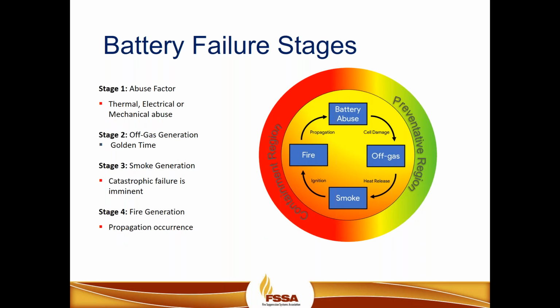So what leads to battery failure? There really are 4 stages that we have to concentrate on when we consider battery failures. The first stage is the abuse factor, and we talked about overcharging and overheating as the 2 main abuse factors that we're going to concentrate on. So of course, overcharging is an electrical abuse and overheating is a thermal abuse. And then we also mentioned the third type of abuse is a mechanical abuse, which is an external factor that we can't really prevent. So where you have direct penetration or damage, an accident, or some type of malfunction in the manufacturing of the device.